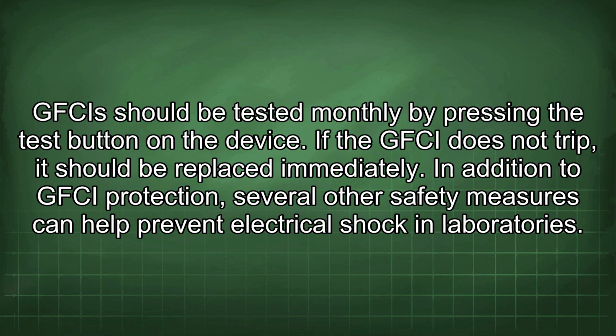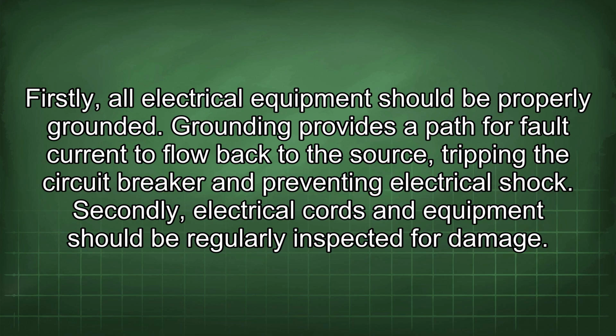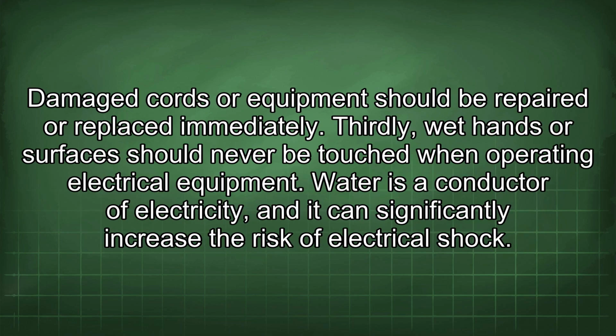In addition to GFCI protection, several other safety measures can help prevent electrical shock in laboratories. Firstly, all electrical equipment should be properly grounded. Grounding provides a path for fault current to flow back to the source, tripping the circuit breaker and preventing electrical shock. Secondly, electrical cords and equipment should be regularly inspected for damage. Damaged cords or equipment should be repaired or replaced immediately.